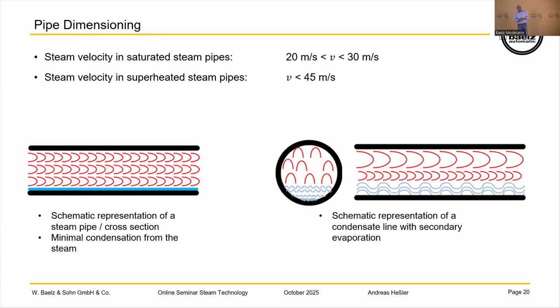For superheated steam, the velocity could be much higher because we have no water and nothing in the pipe. So we're going up to 45, sometimes to 50 or 60 meters per second, because you have no issues with water droplets or condensate inside the pipe. So it would be good for the piping. If you have hot condensate where there could be some steam inside the piping, it would be good to have no more than 0.5 meters per second or 1 meter per second. Don't go higher because you have some flashing, like in the right pictures. A steam water mixture is not good for the piping, it would be destroyed.